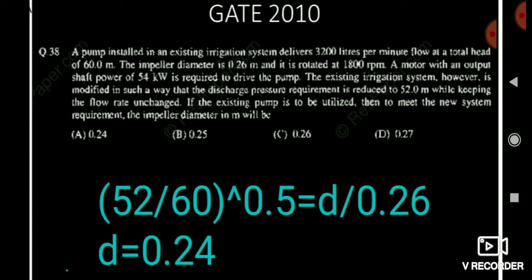To meet the new system requirement, we need the new impeller diameter. H1 = 60 m, H2 = 52 m, and D1 = 0.26 m are given; D2 is asked. Since pressure is proportional to diameter squared, we use: (H2/H1) = (D2/D1)², so (52/60) = (D/0.26)². Taking square root (power of 0.5), we calculate and get D2 = 0.24 meter.